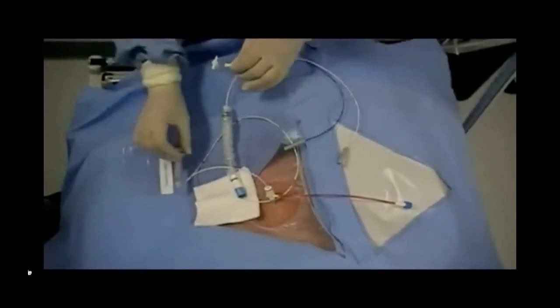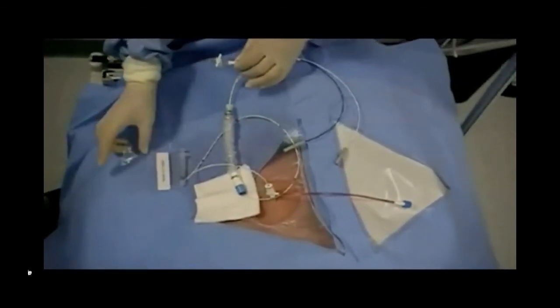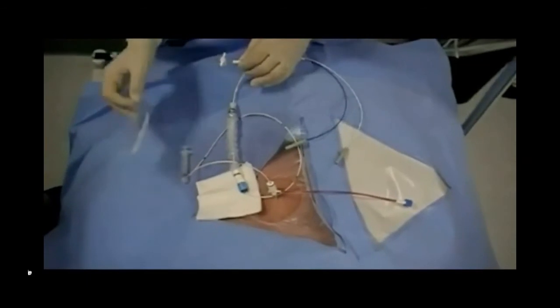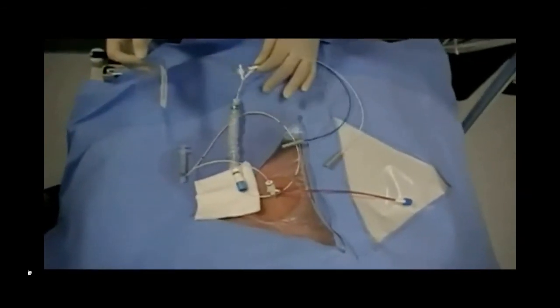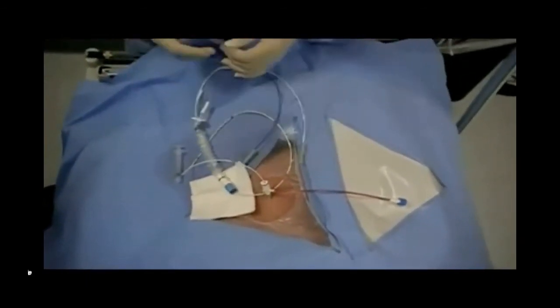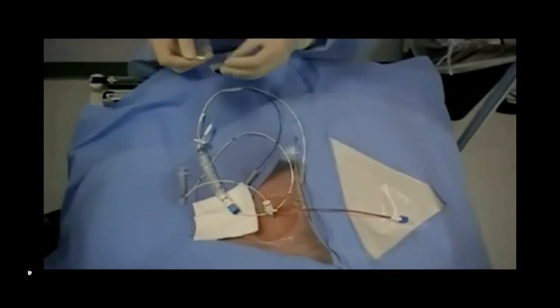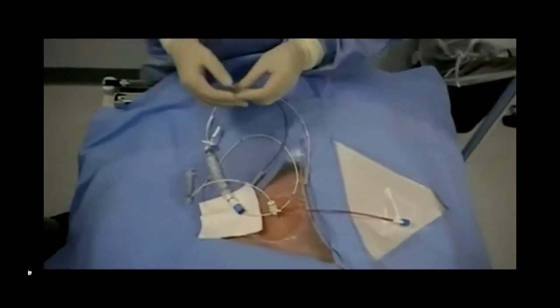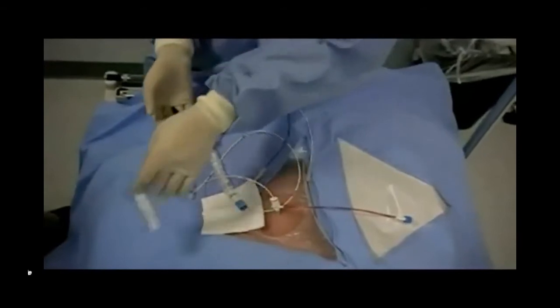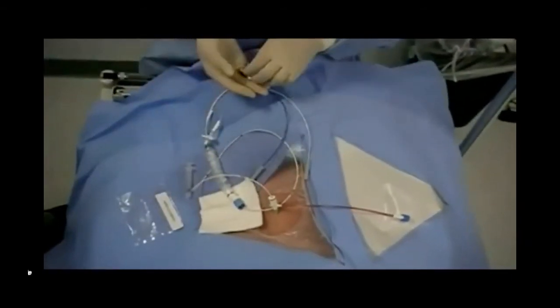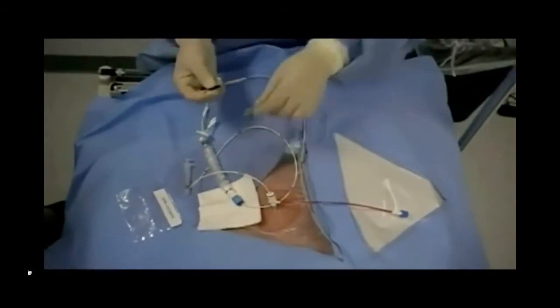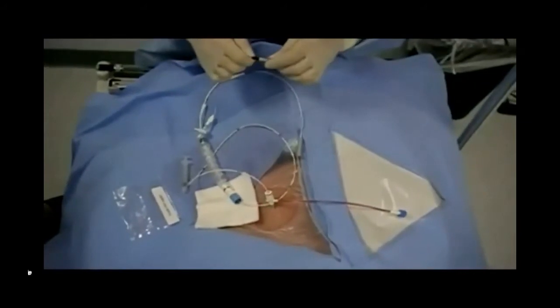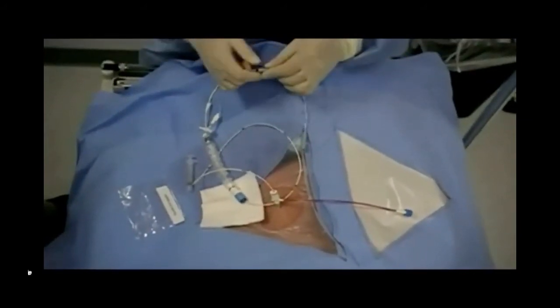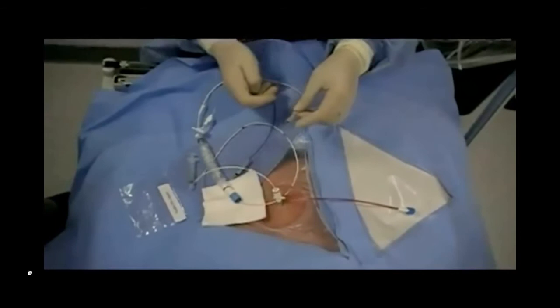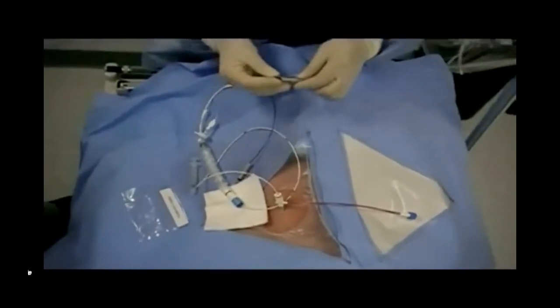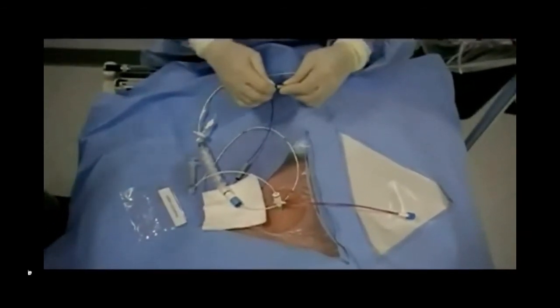The valve must be turned to the locked position to maintain balloon inflation. The balloon allows the wire to float gently into place and reduce the likelihood of intimal damage. Once the balloon is inflated, the sterile operator should open the package with the adapters that connect to the proximal end of the pacing wire. Once the adapters are inserted, the proximal end of the catheter can be handed off to a non-sterile operator.